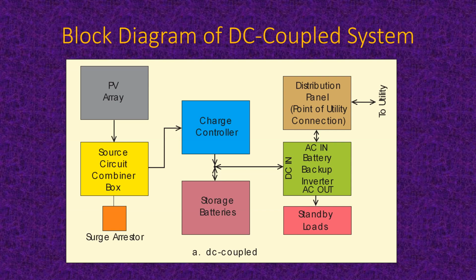The charge controller makes sure the batteries don't get overcharged, and if there's nowhere for that electricity to go from the solar array, the batteries are full and nothing else wants it, then it shuts down the array. Notice the directions of the arrows here. Some are unidirectional, some are bidirectional. And here we come to a couple of bidirectional. That means that the storage batteries, we can either charge them or discharge them as needed. And the power that flows from that junction between the charge controller and the storage batteries can either go to or from the battery backup inverter.